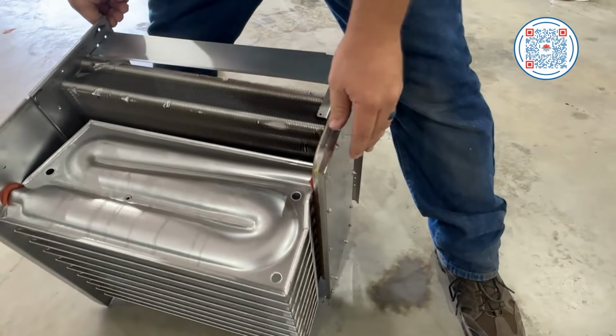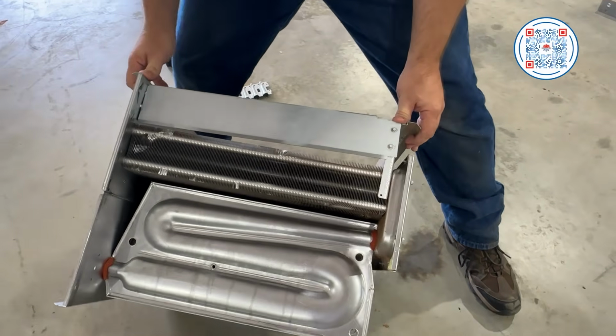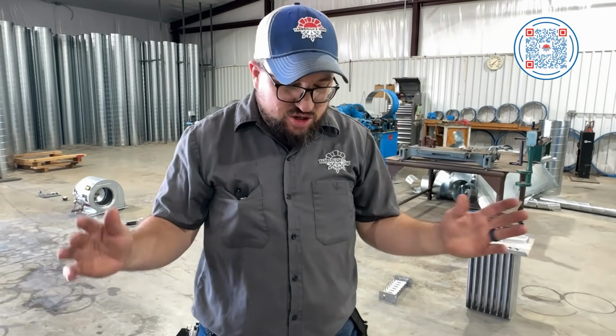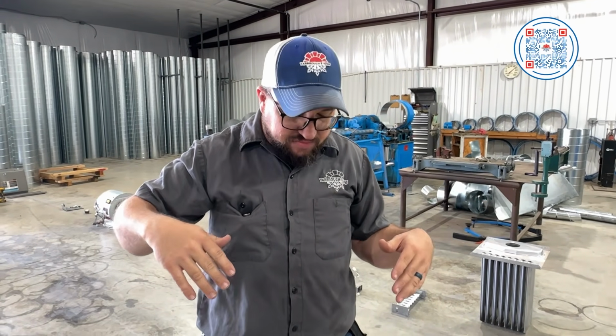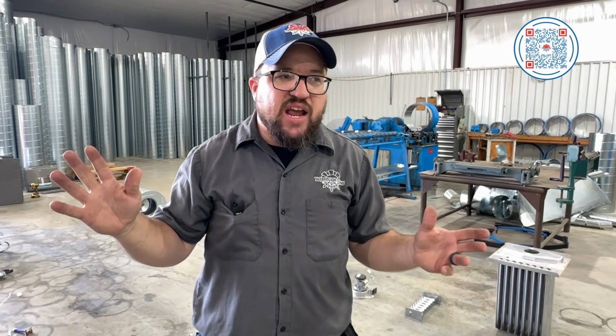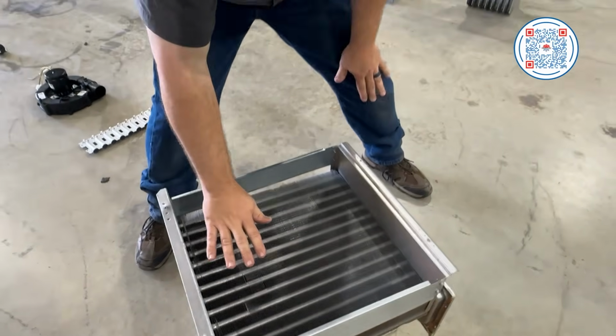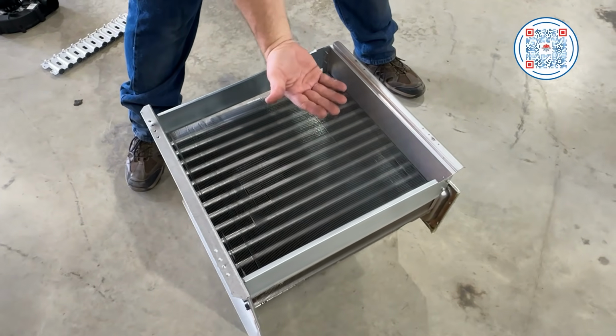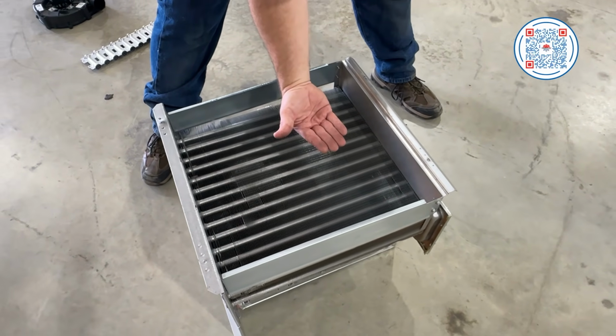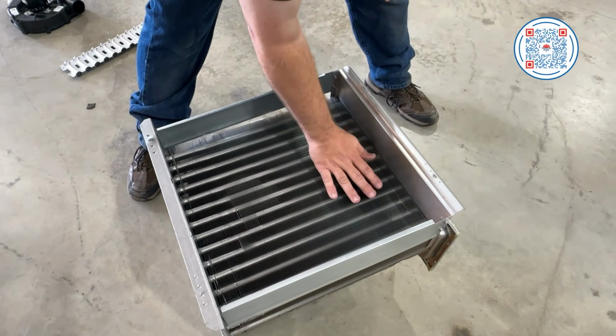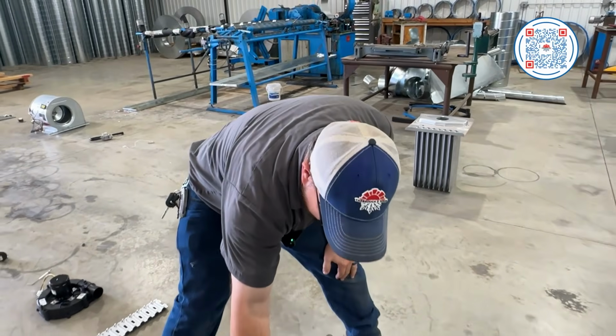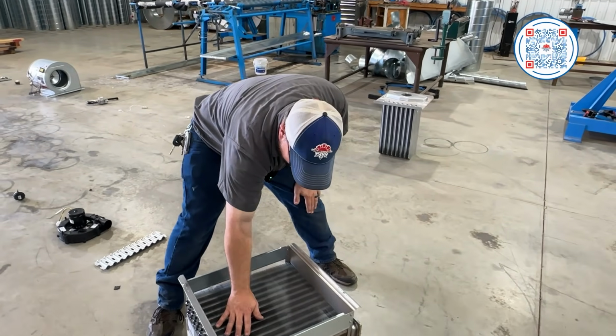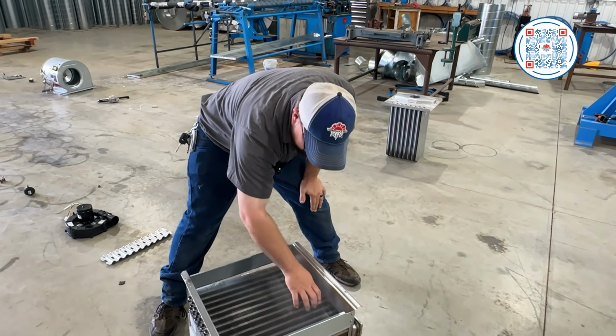So, amazing technology. I would say the biggest problems that we have with these have to do with maintenance. Seems like we're always pushing maintenance, but it's true. I have had units where the unit won't run. It's going off, you know, it's hitting my high limit and stuff like that. And then you pull the blower, and this secondary heat exchanger sits right next to the blower. So that blower is blowing right here, and before it goes in the coil, it goes into this light coil. So this coil right here, the secondary heat exchanger, can get dirt built up on it.